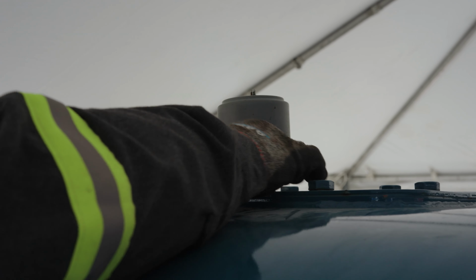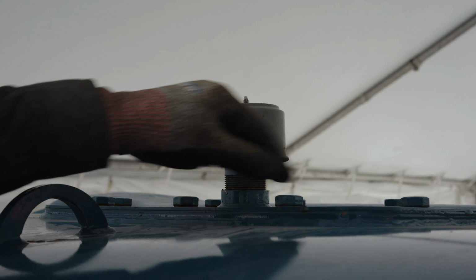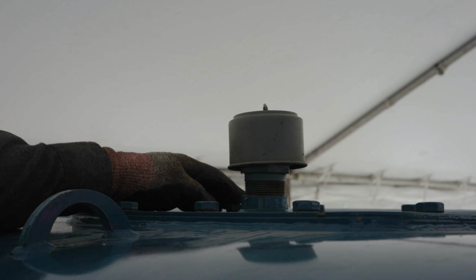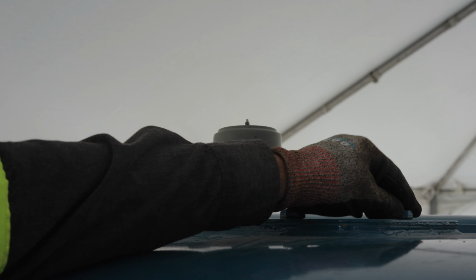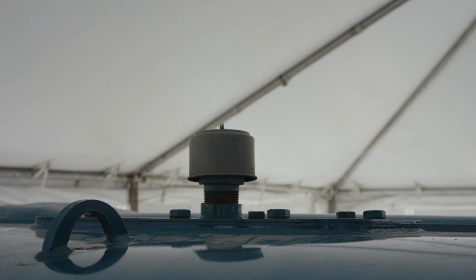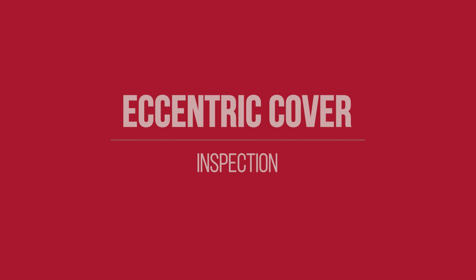On the top of the pump, you will find an inspection plate and breather. Check the serviceability of the breather. Make sure it is not loose or broken. Also check the studs and check for a leaky gasket on the inspection plate. If oil can come out, water can get in.